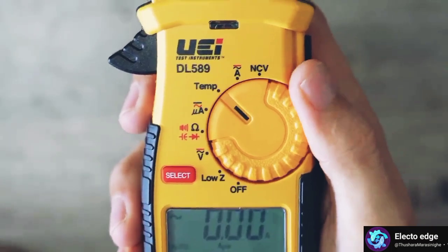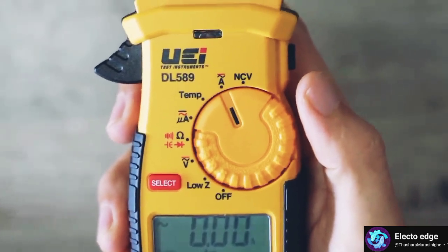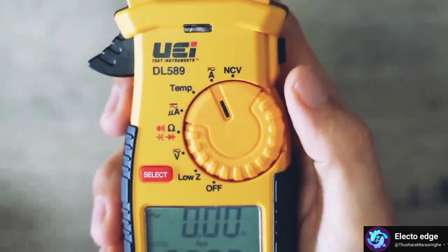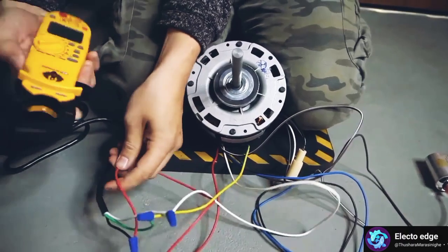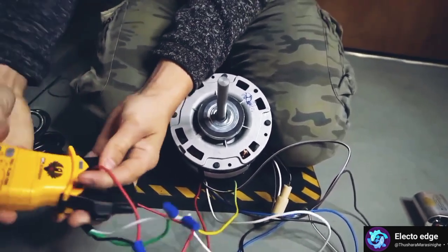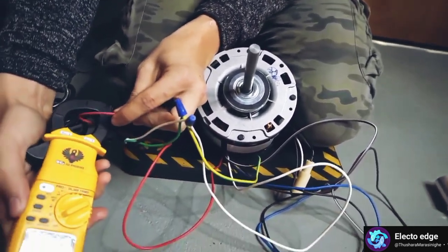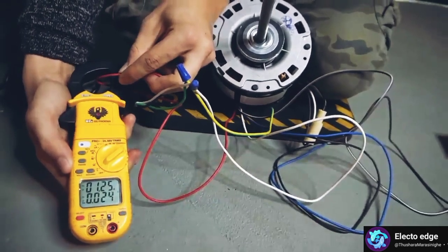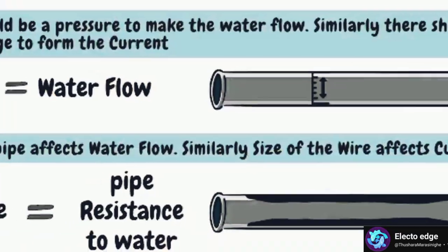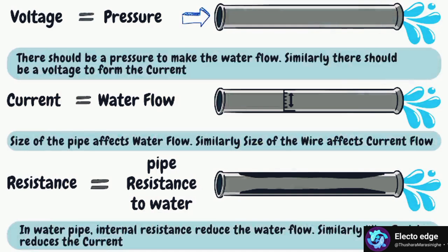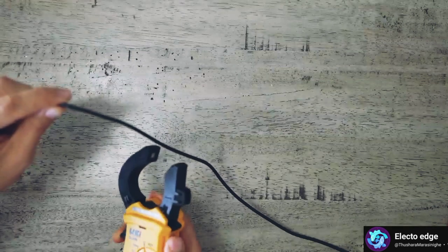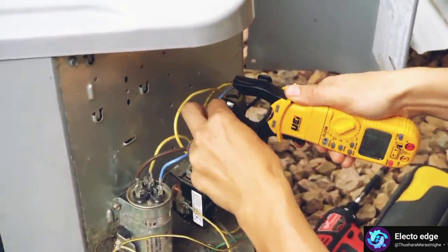Next up is amperage, and this is used to test how much current an electrical device or a motor is drawing. The easiest way to check the amp draw of something, whether it be a motor or some other electrical device, is to use the amp clamp. If we compare electricity to plumbing, the voltage would be equivalent to the water pressure, whereas the current, the amperage, is equivalent to the flow rate, the gallons per minute. So when you put your amp clamp around a wire that is powering some electrical device, you will see how much current is flowing through that wire.